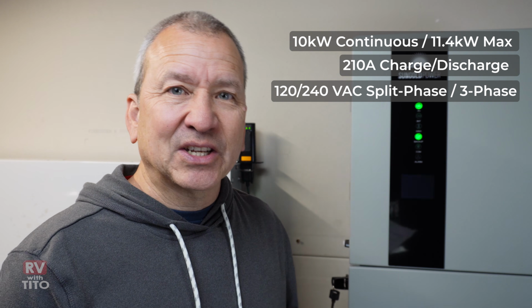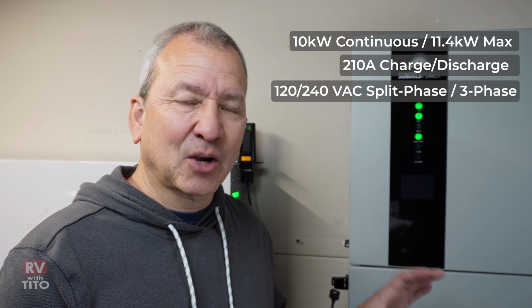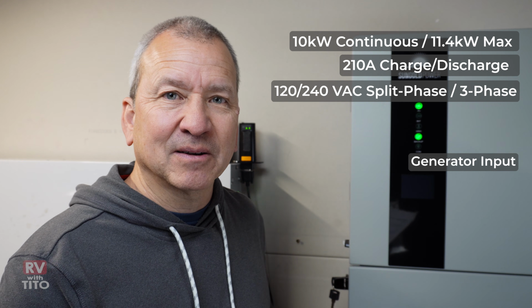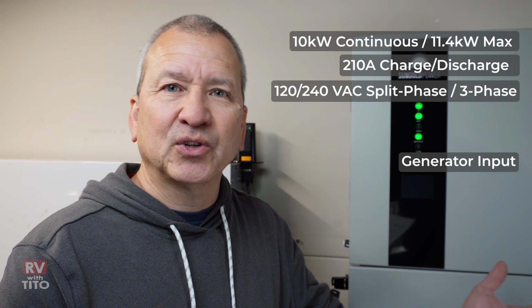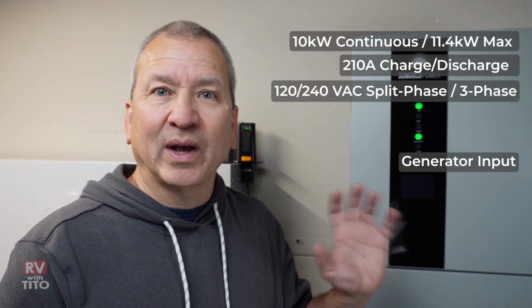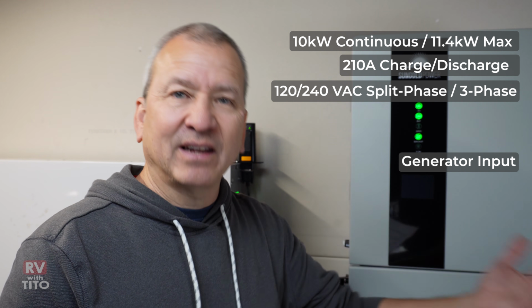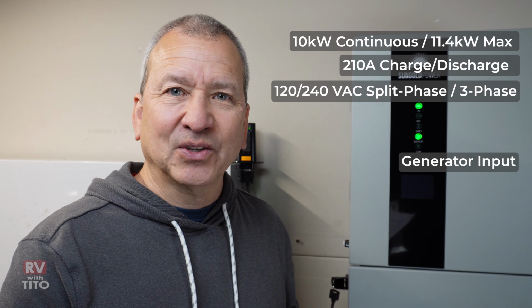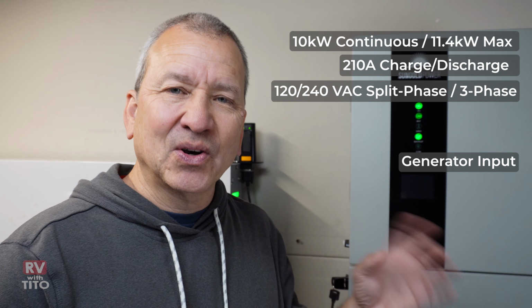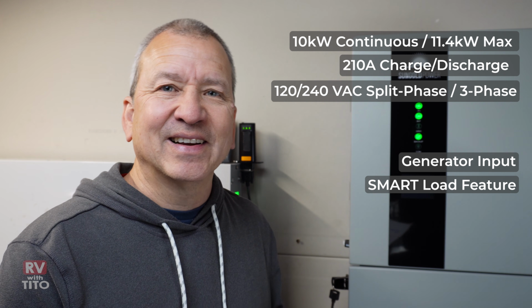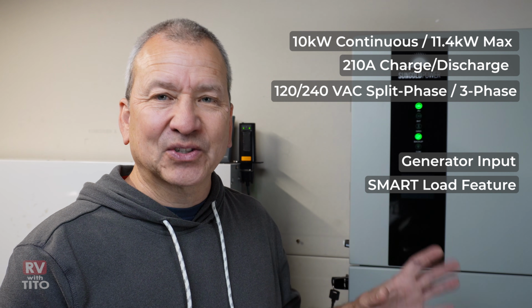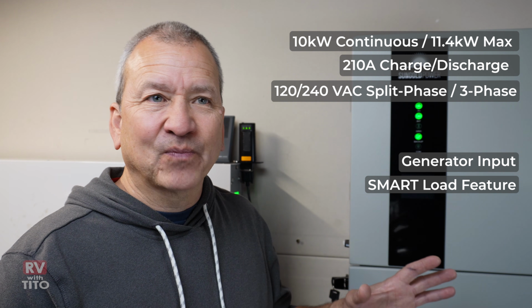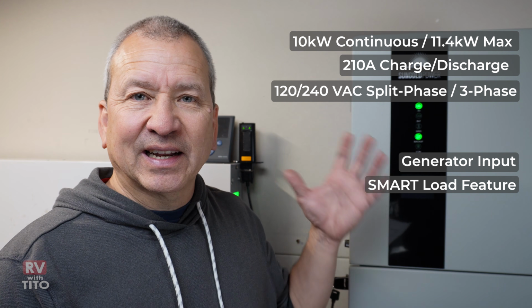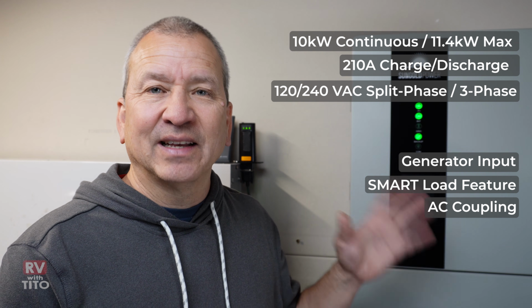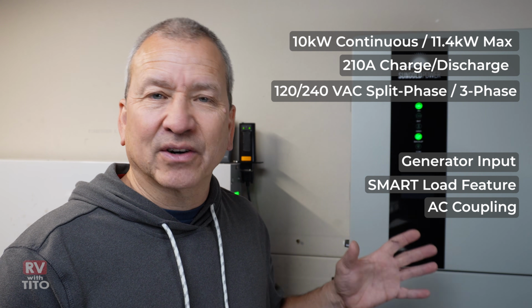Now it also has some additional inputs and outputs that I'll talk about when we get into the box here. But we can plug in a generator to it, program how and when that generator is going to kick in and cut out, and also it's got this thing called a smart load, which I'll talk about. And we can also, like I mentioned, set it up so you can connect a grid tie inverter to it and use it to charge batteries.